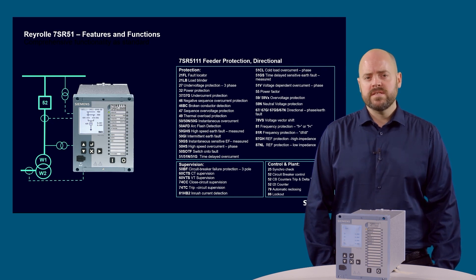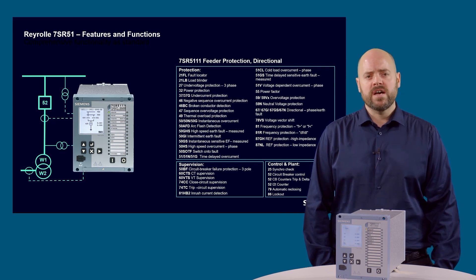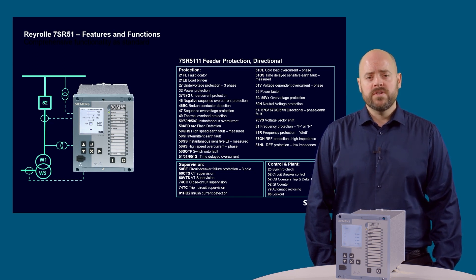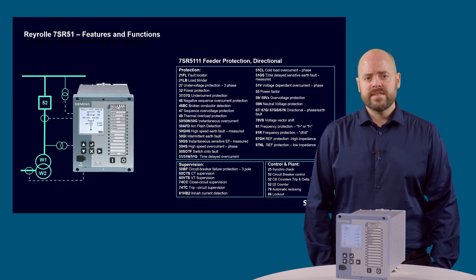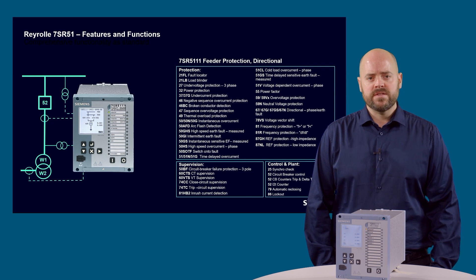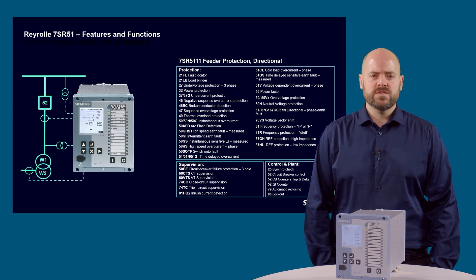The 7SR5111 directional overcurrent and directional earth fault protection devices are used in interconnected systems. As standard these have 4CT inputs and 4VT inputs, allowing additional functionality over the 7SR5110. Also available are 7SR5121 devices with 5CT inputs, typically used in transformer circuits, providing overcurrent and earth fault functions as well as measured standby earth fault to protect the earthing resistor and high-impedance earth fault protection for the transformer winding.